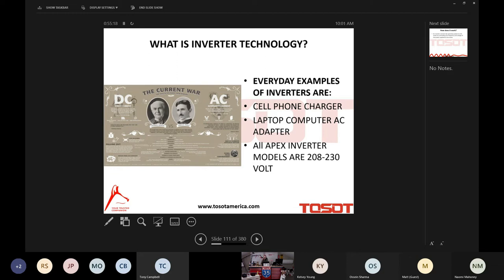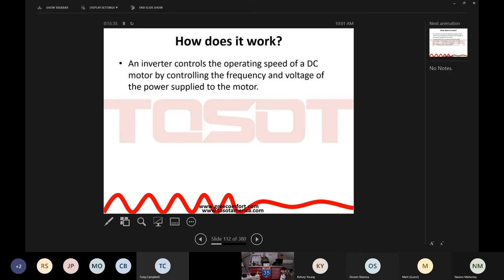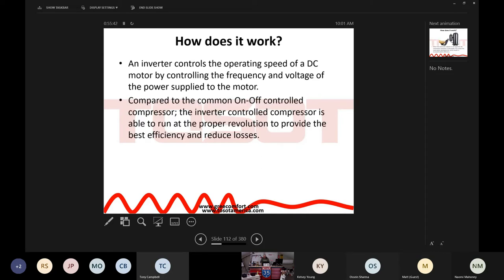The Apex inverters are all 208, 230 volts. We do have some exception to that in the mini split world, with some 115 volt product, which I love that Tosot still makes that available. But in the Apex, everything is 208, 230 volt. So guys, an inverter controls the operating speed of a DC motor by controlling the frequency and the voltage of the power supplied to that motor. Compared to the common on-off control compressor, the inverter control compressor is able to run at the proper revolutions to provide the best efficiency and reduce losses.